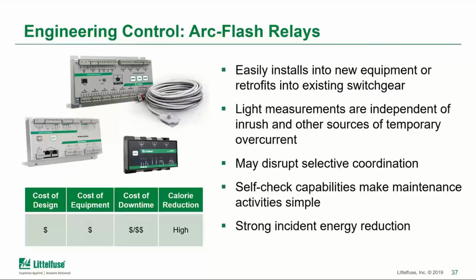So the arc flash relays tend to be a standalone piece of equipment, and the cost of design to put them into the equipment is generally fairly low. Once the study is conducted, adding the arc flash relay generally can be layered in on top with existing breakers, existing equipment, and take advantage of that calorie reduction. The cost of the equipment is generally also fairly low, as the arc flash relays and sensors can be installed in the equipment and not need too many different components in most standard sizes of equipment.